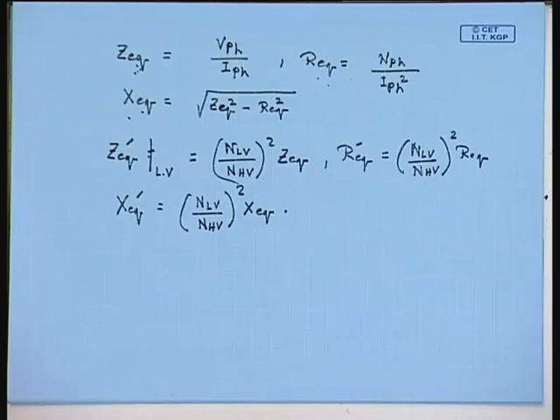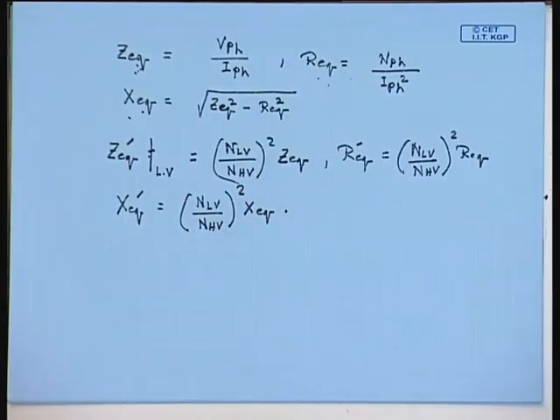Alternately, all the parameters may be expressed in per unit form with the bases selected as the power base to be selected as the 3-phase power rating of the transformer, and the voltage bases from either side can be selected as the rated line to line voltage of the high voltage and low voltage side respectively. If you do that, then the parameters that we obtain can be used without further referring by turns ratio.